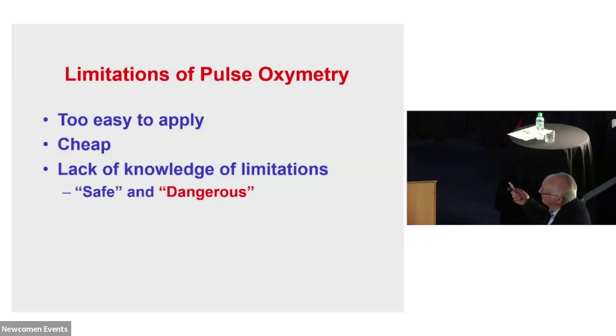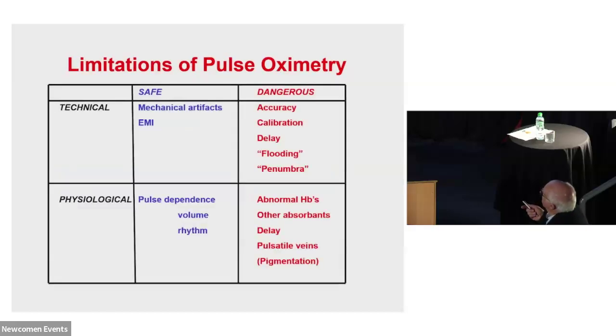And by the way, I was going to do this lecture somewhere else 3 years ago, because it's the 53rd anniversary this year of pulse oximeters. But that's beside the point, really. So the limitations I've split up into safe down here and dangerous here. The safe ones are that you can see what's going on. And the only way you can do it really is that whatever pulse oximeter you're using, whether it's a little one on a finger or a rack-mounted one, you must be able to see the trace, the up and down trace of the pulse oximeter indication of the plethysmograph. If you can't see that, then it's not safe.